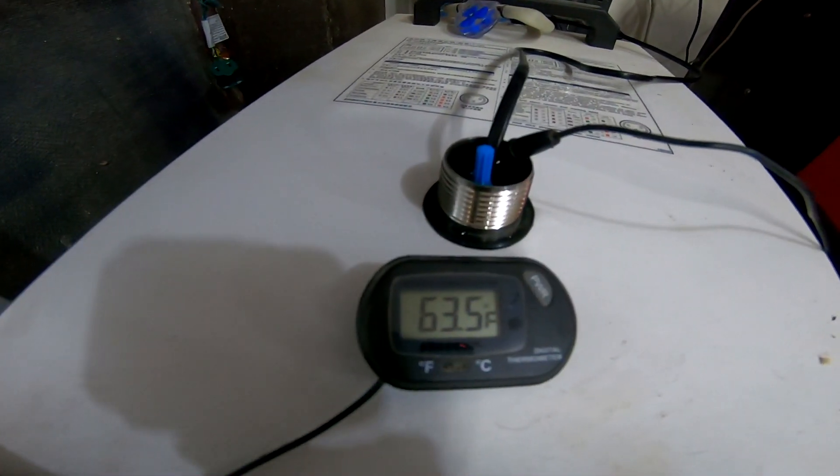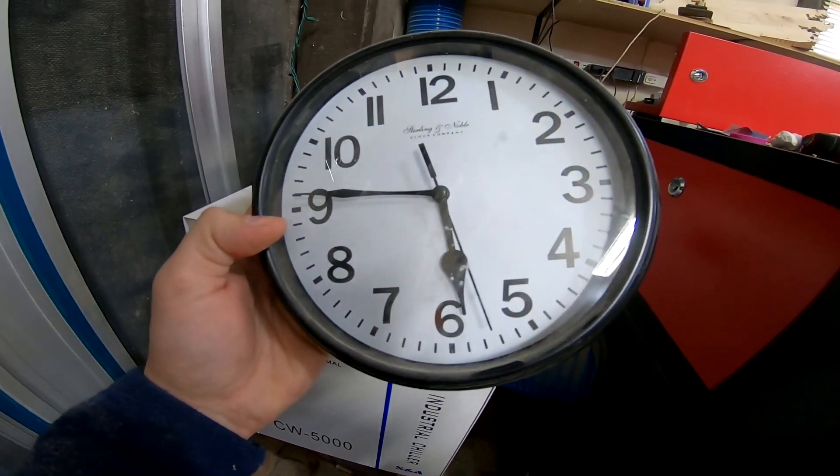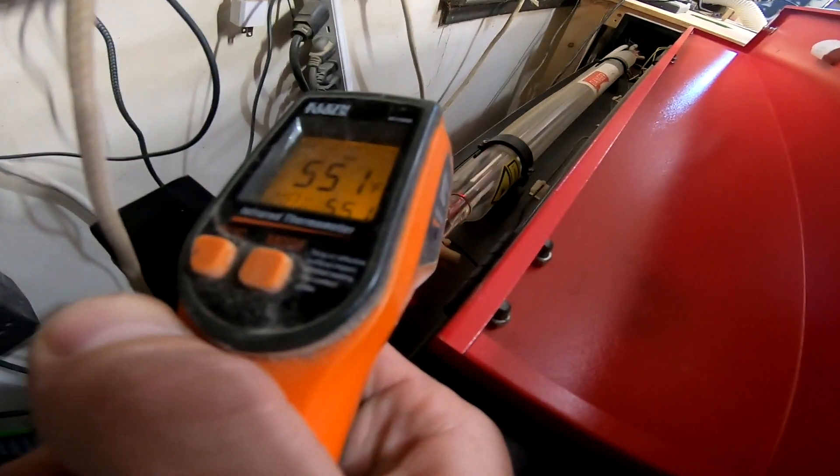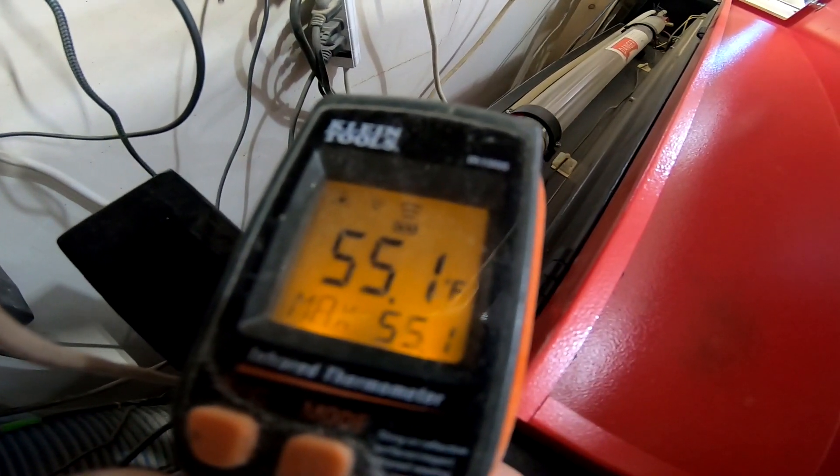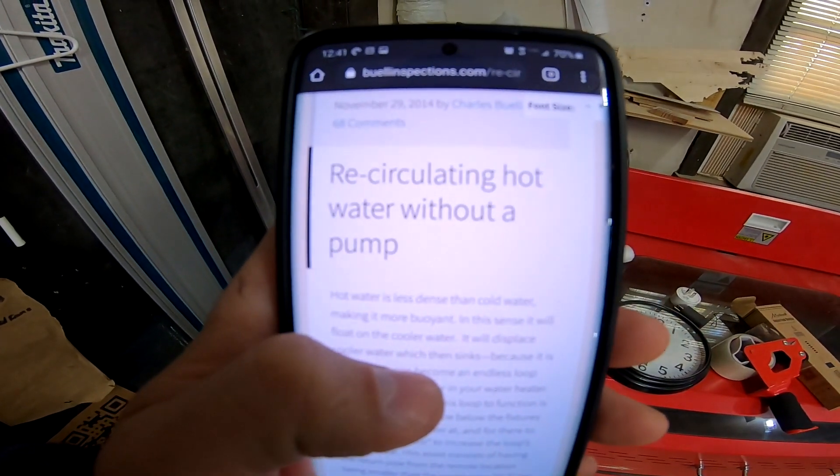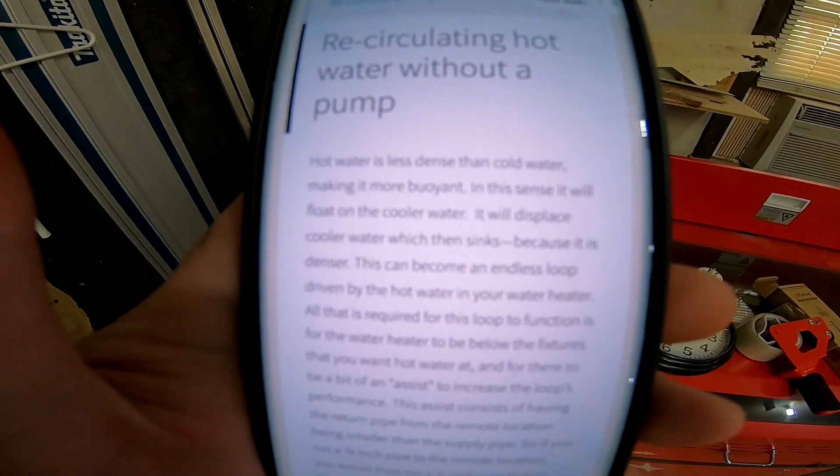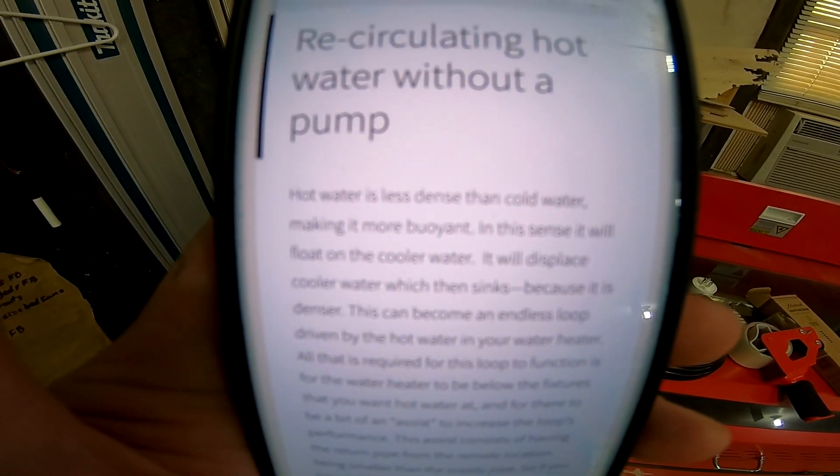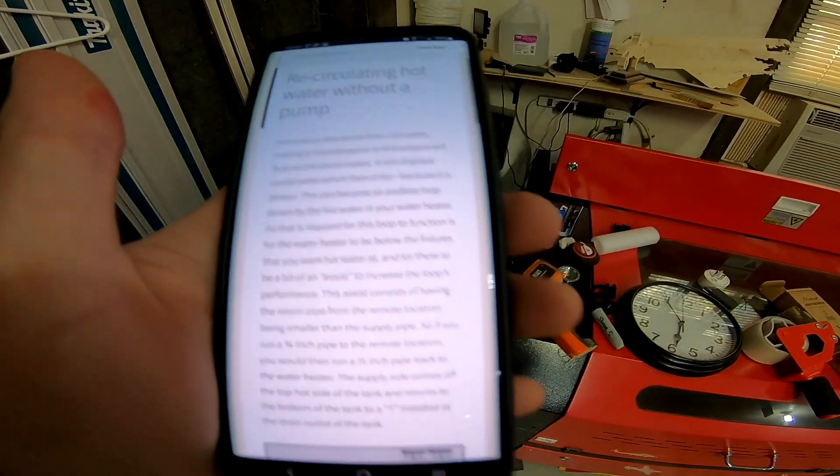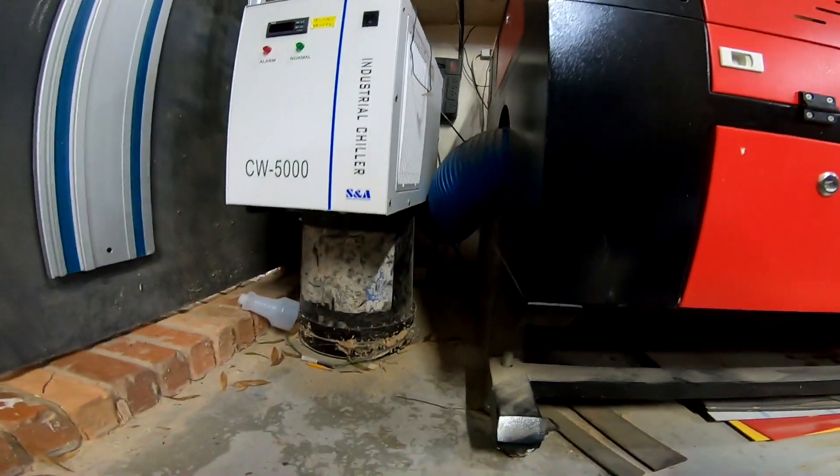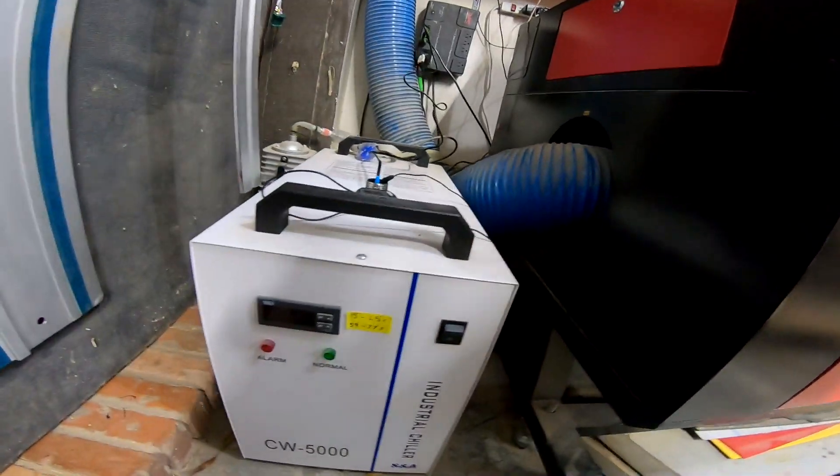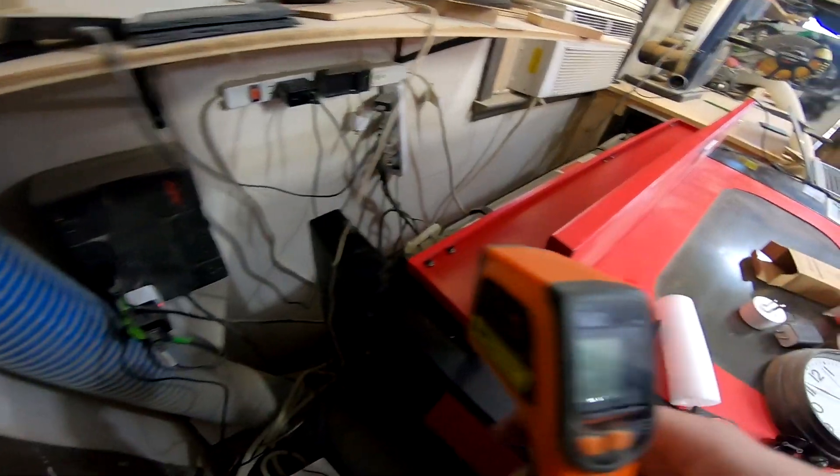The temperature is now in range, and it only took about 25 minutes inside the chiller itself. My hope was that, with the temperature being warmer in the chiller, the water would flow through and get to the tube itself, because warm water will rise and cold water will sink. But I believe that with this laser system, there is a flow sensor that is stopping that from happening passively on its own.